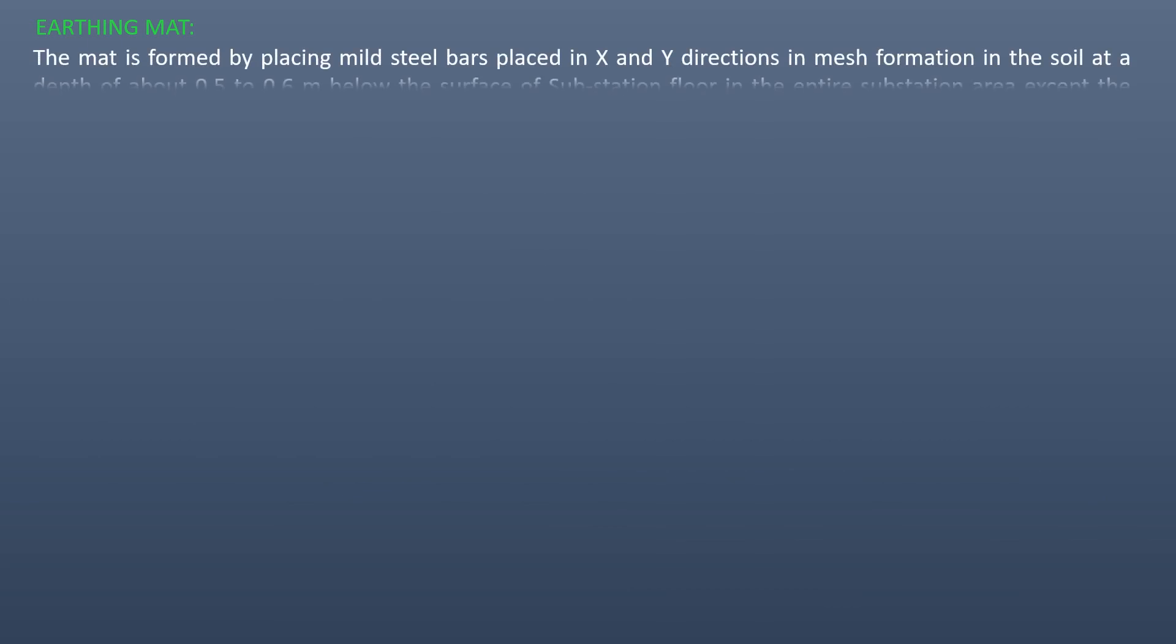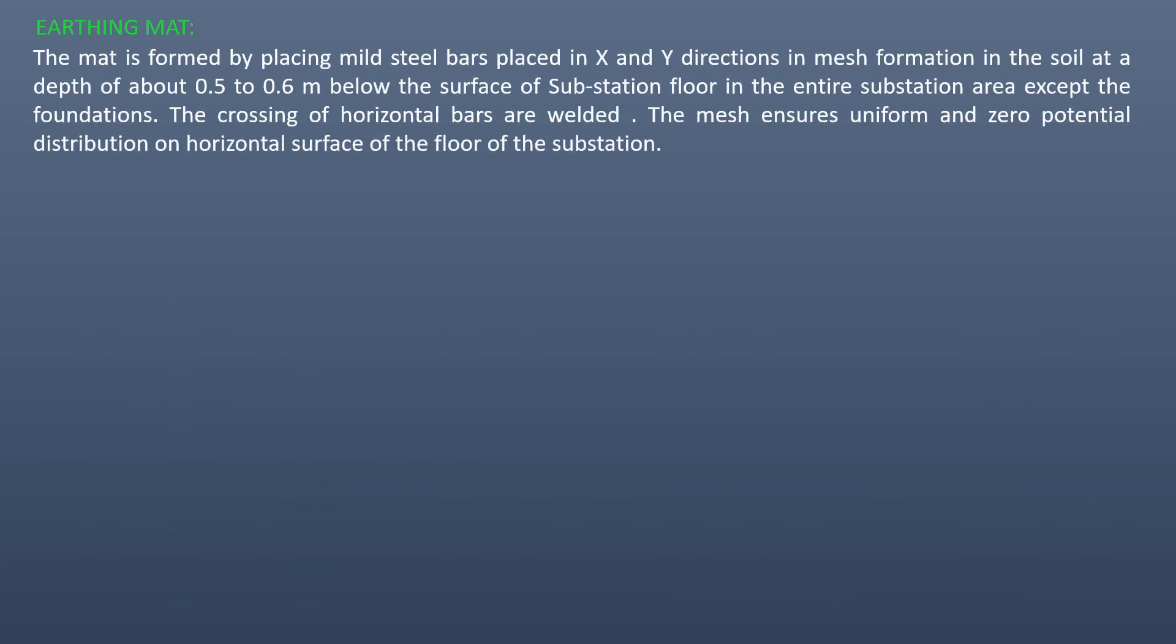The mat is formed by placing mild steel bars placed in X and Y directions in mesh formation in the soil at a depth of about 0.5 to 0.6 meter below the surface of the substation floor in the entire substation area except foundations. The crossing of horizontal bars are welded. The mesh ensures uniform and zero potential distribution on horizontal surface of the floor of the substation.